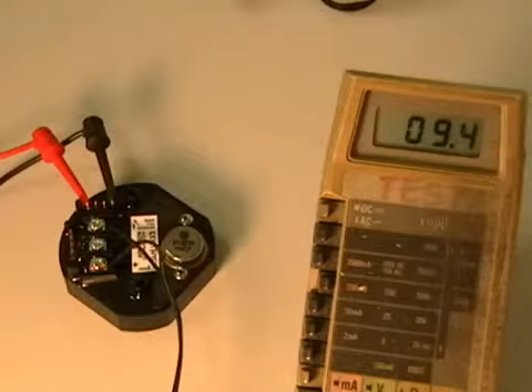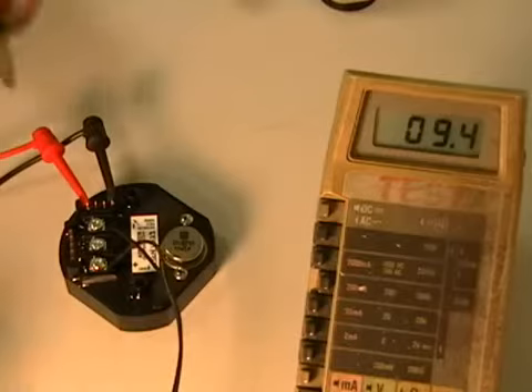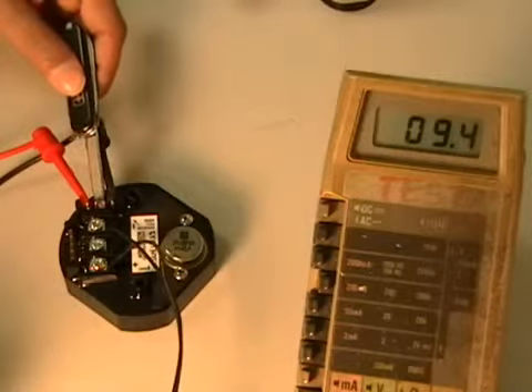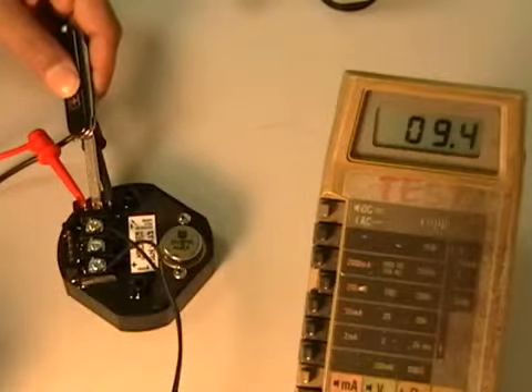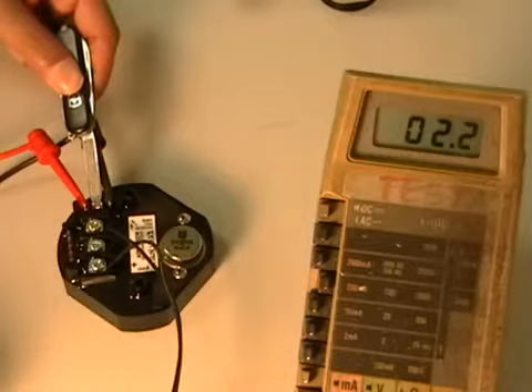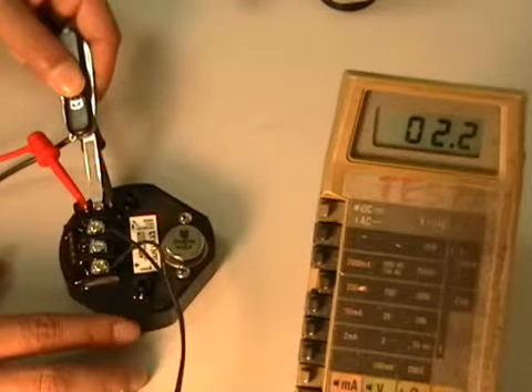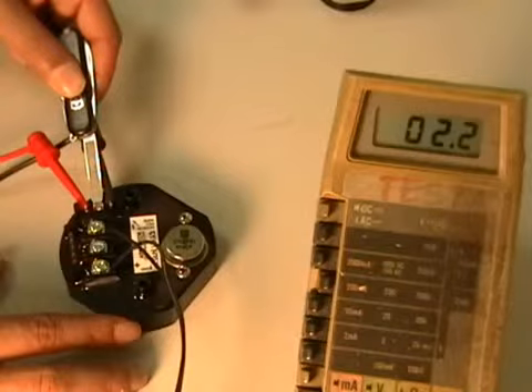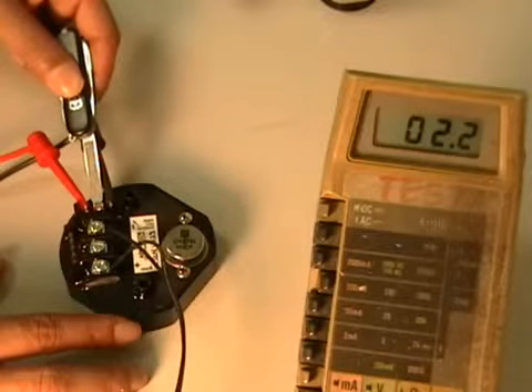Using a conductive tool such as a screwdriver or knife tip, short the two center pins on the 4-pin header. The voltage should drop to approximately 2 to 2.5 volts. We now have verified that the transmitter can vary the voltage from 2 to 9 volts depending on the specific coding resistor value of the sensor used.